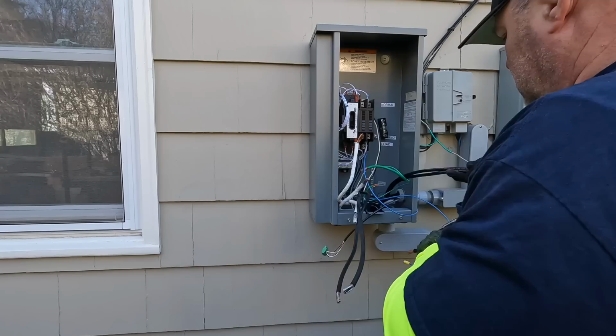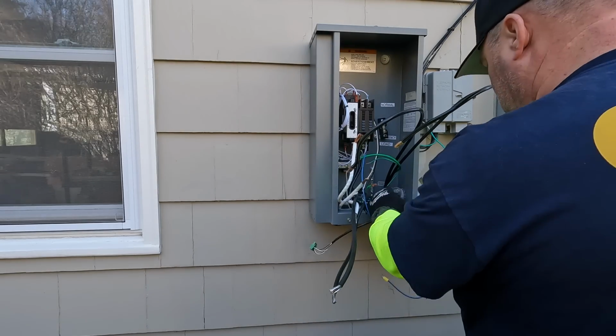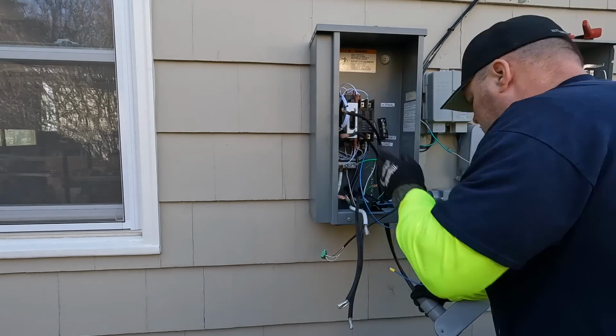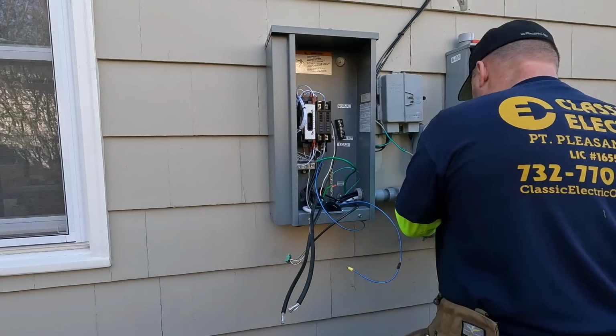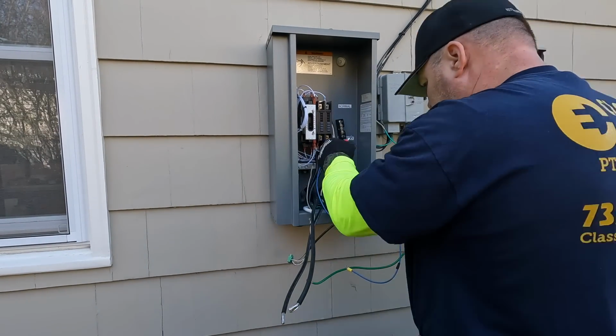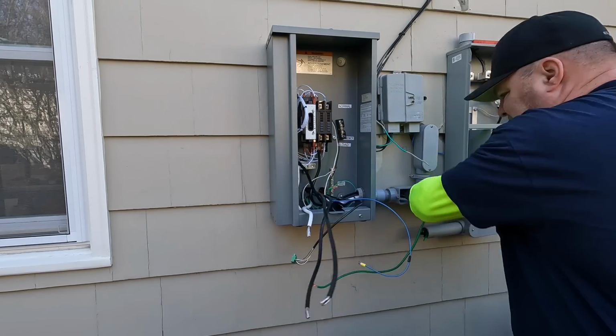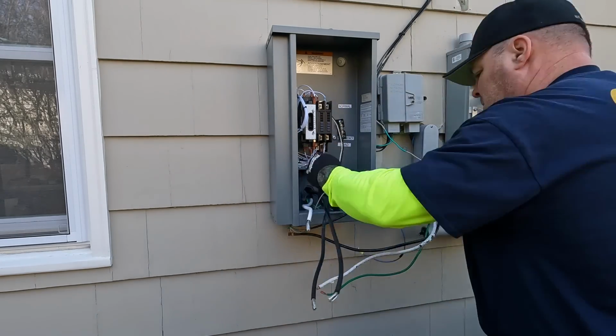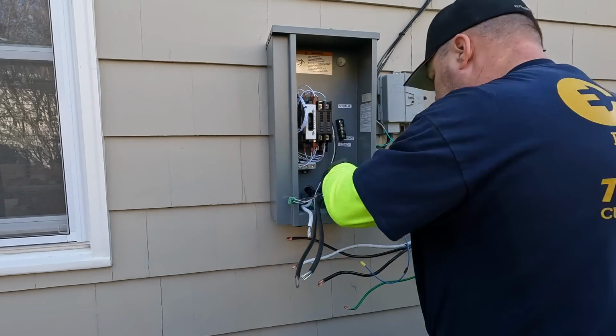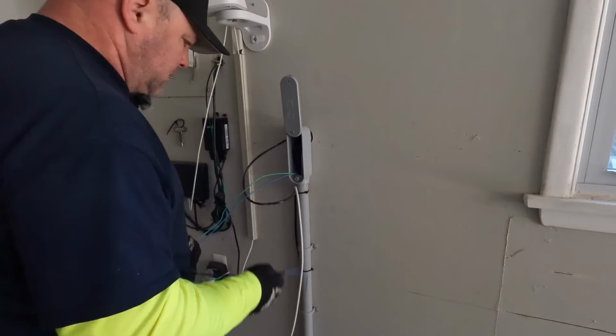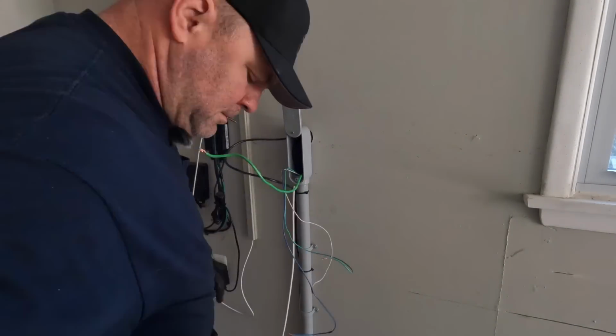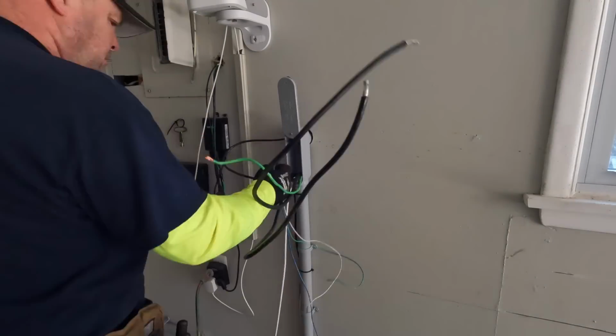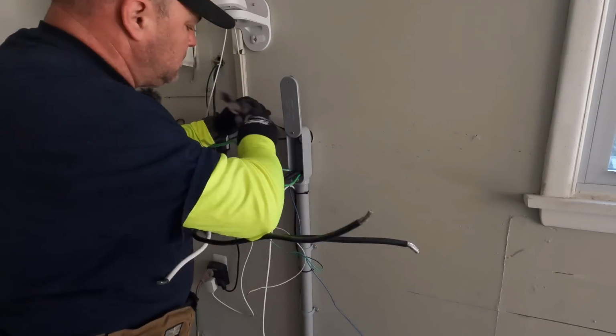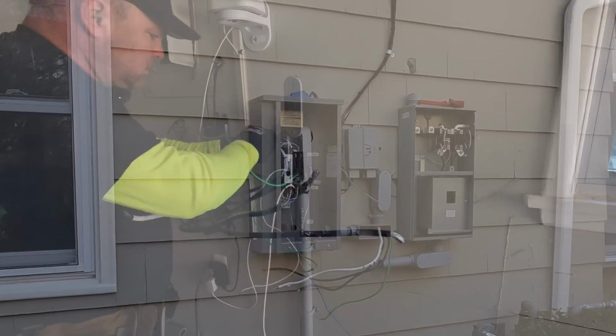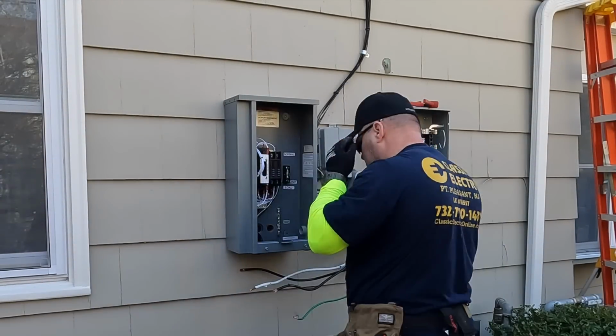I'm not totally familiar with all the wiring that goes on with Kohler standby generators. I had to buy the 200 amp transfer switch for this job, and I read the paperwork, and it wasn't really that complicated. It's not that much different than Generac, but it is different as far as load shedding. Inside this transfer switch is a module, a current transformer, which acts as the load shedding part of the process for a Kohler generator. That's a little different than what we do with Generac. I got more training and experience in Generac, but I was able to handle this, and it was not a problem.